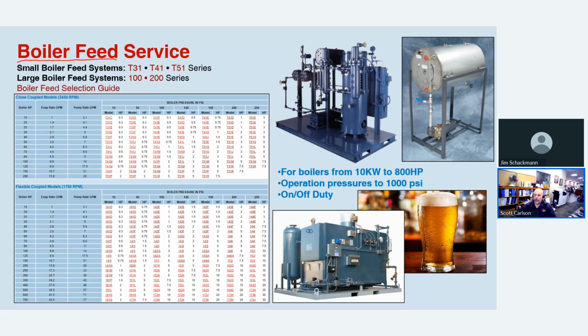So we've come up with this chart that's our boiler feed selection chart, that if you can find out what the boiler horsepower is and then find out what the PSI inside the system is that it needs to overcome, we have pre-selected several pumps all the way up to 700 horsepower boilers and 250 PSI. And there's some other ones that we can do besides that. We would just have to custom size them up for you, but this is available right on our website.